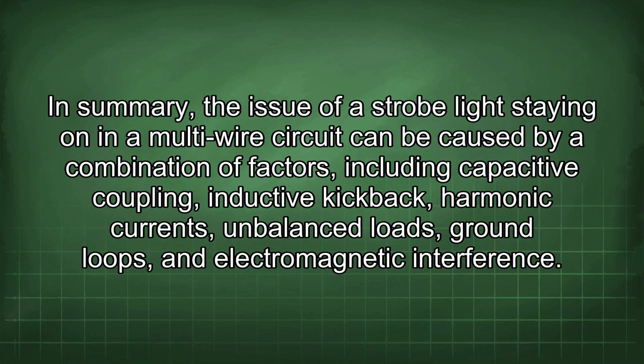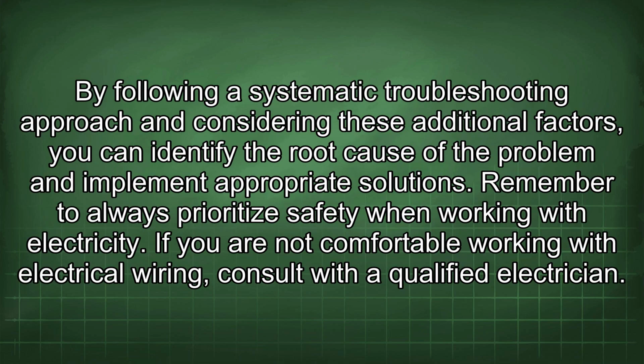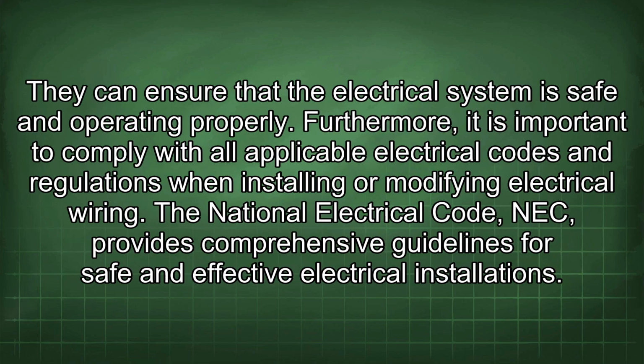In summary, the issue of a strobe light staying on in a multi-wire circuit can be caused by a combination of factors, including capacitive coupling, inductive kickback, harmonic currents, unbalanced loads, ground loops, and electromagnetic interference. By following a systematic troubleshooting approach and considering these additional factors, you can identify the root cause of the problem and implement appropriate solutions. Remember to always prioritize safety when working with electricity. If you are not comfortable working with electrical wiring, consult with a qualified electrician. They can ensure that the electrical system is safe and operating properly.